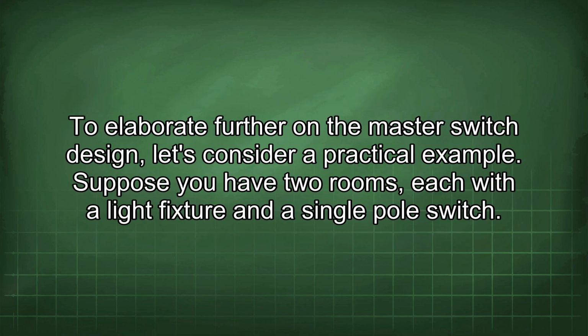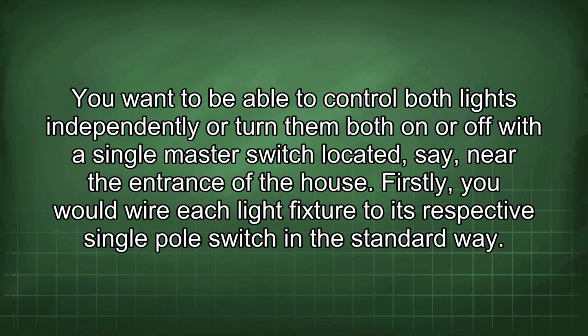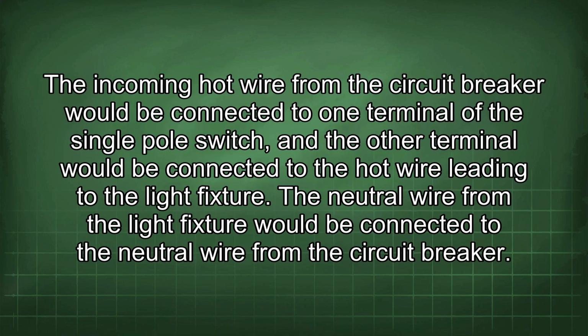To elaborate further on the master switch design, let's consider a practical example. Suppose you have two rooms, each with a light fixture and a single-pole switch. You want to be able to control both lights independently or turn them both on or off with a single master switch located, say, near the entrance of the house. Firstly, you would wire each light fixture to its respective single-pole switch in the standard way. The incoming hot wire from the circuit breaker would be connected to one terminal of the single-pole switch, and the other terminal would be connected to the hot wire leading to the light fixture. The neutral wire from the light fixture would be connected to the neutral wire from the circuit breaker.